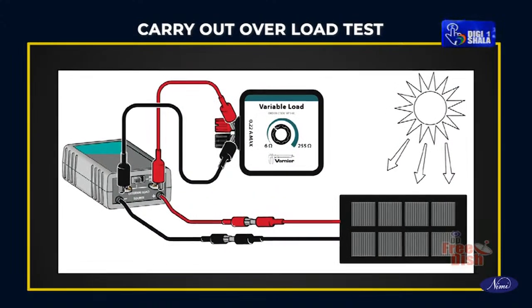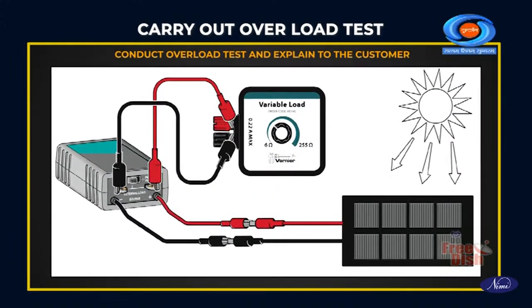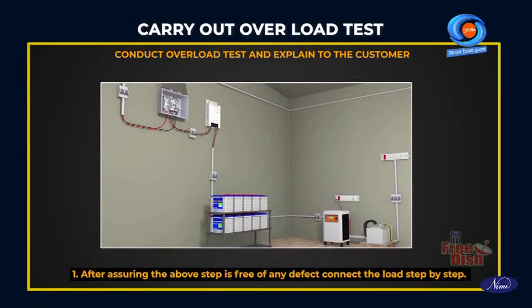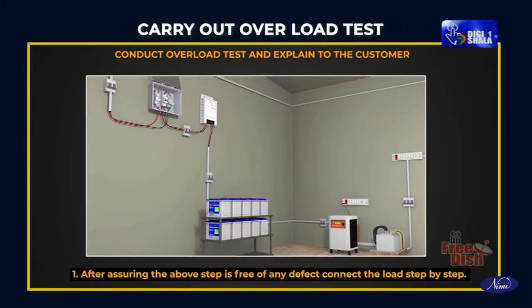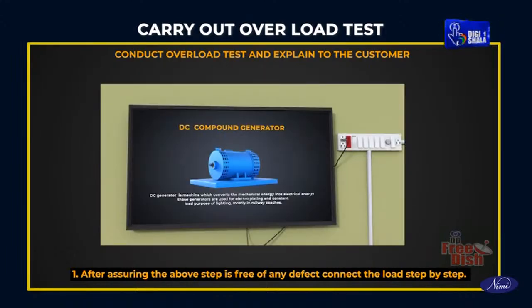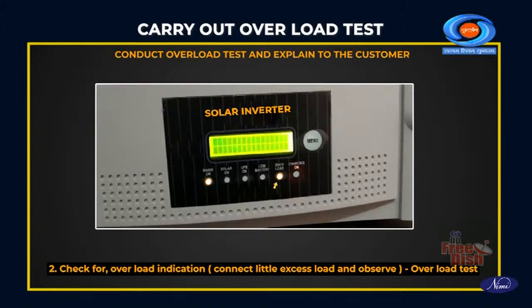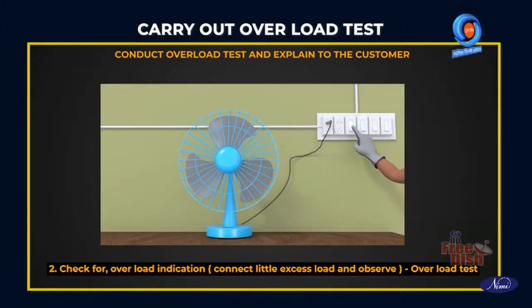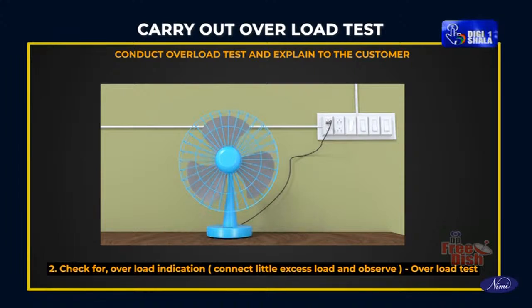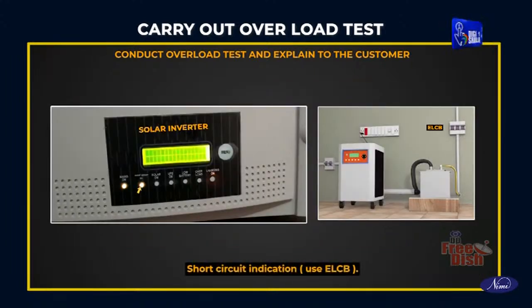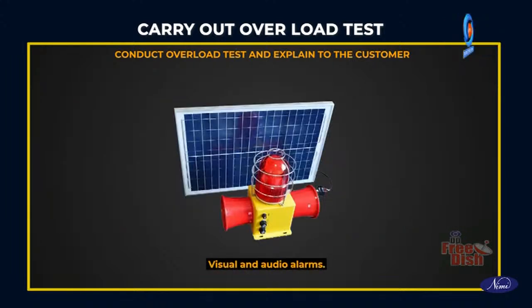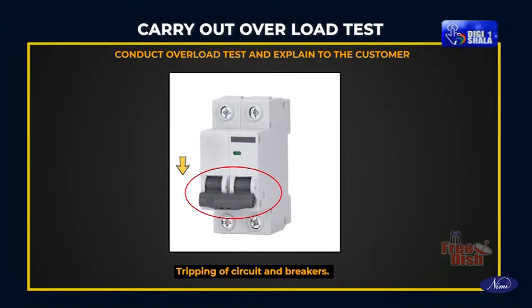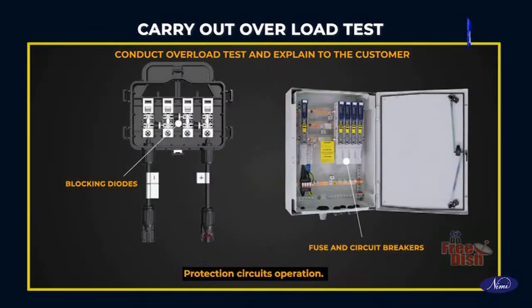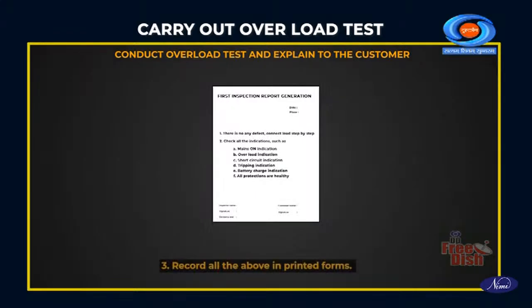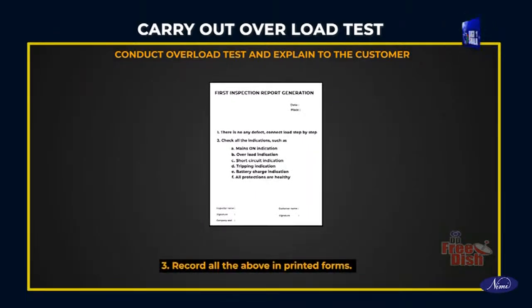Carry out overload test. Conduct overload test and explain to the customer. After assuring the above steps are free of any defect, connect the load step by step. Check for overload indication. Connect little excess load and observe. Overload test. Short circuit indication. Use ELCB. Visual and audio alarms. Tripping of circuit and breakers. Protection circuits operation. Record all the above in printed forms.